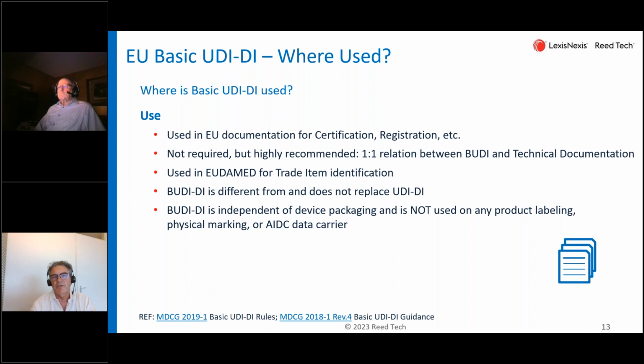So I think it's very important to understand that there's not a strict legal requirement to have a one-on-one relation between the Basic UDI and the technical documentation, but I strongly recommend doing it. If you do it, be very careful, because you may end up with much more work to keep your technical documentation updated if things start changing in the future. So on the short term, yeah, that looks like a quick gain. On the long term, you may have worked yourself into a difficult situation.